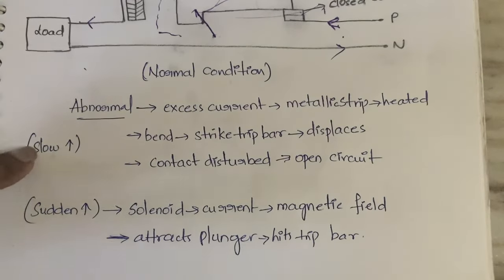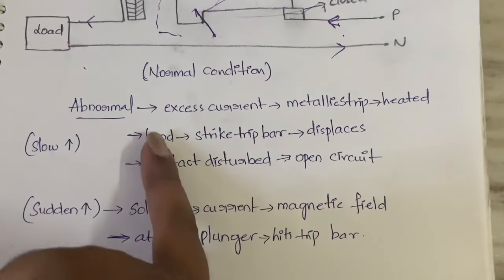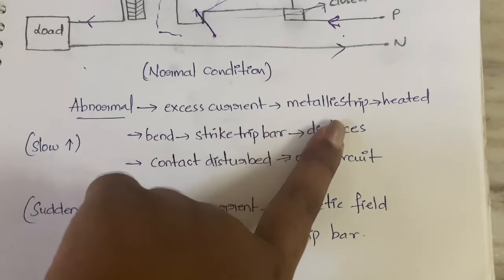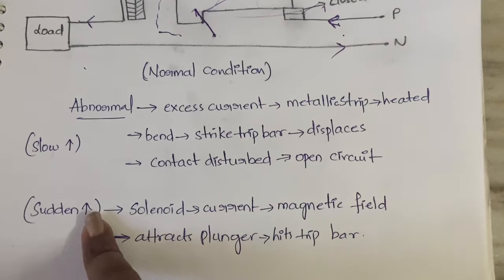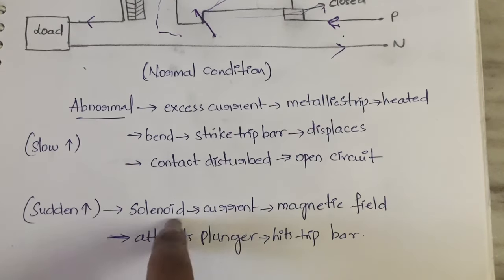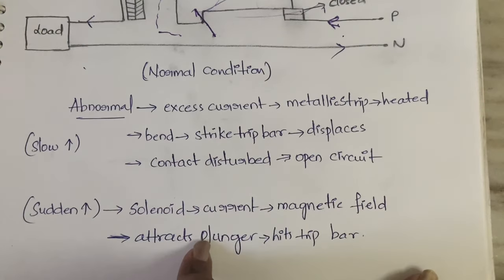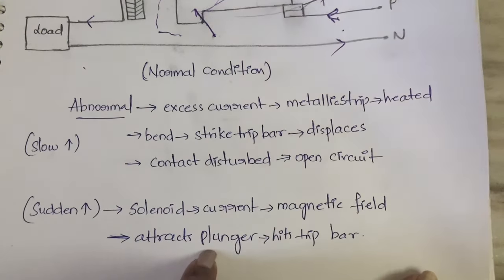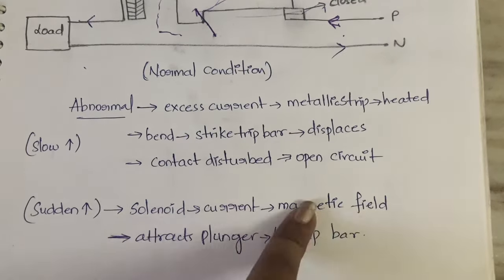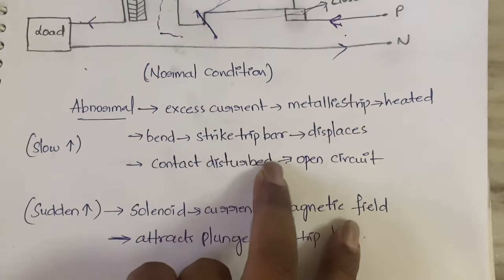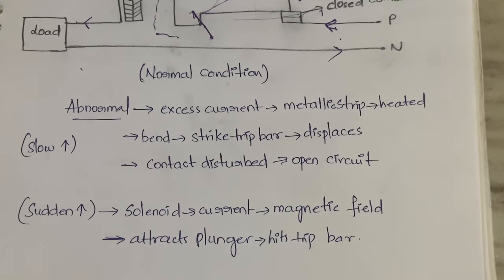To summarize — you can take a screenshot of this: In case of slow increase in current, the bimetallic strip heats up, bends, strikes the trip bar, the trip bar displaces, the contact is disturbed, and it becomes an open circuit. In case of sudden increase, current passes through the solenoid, a magnetic field is generated, the magnetic field attracts the plunger, the plunger hits the trip bar, the contact is disturbed, and it becomes an open circuit. That is all about MCCB.